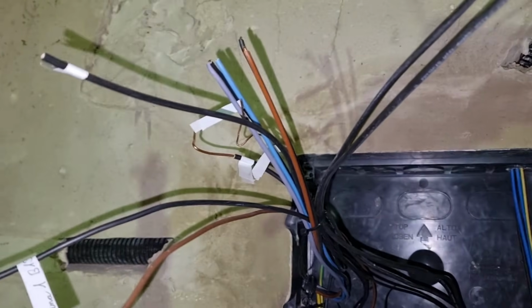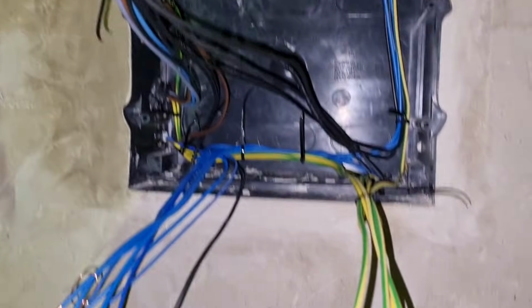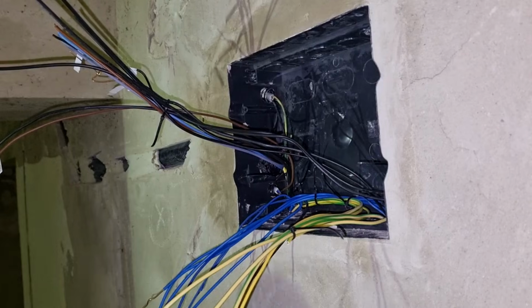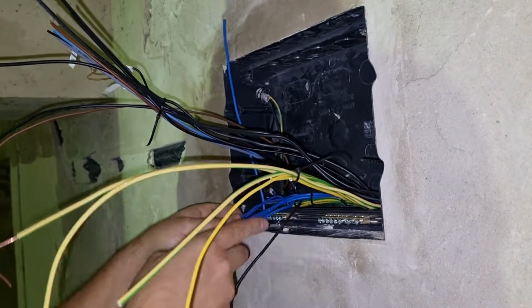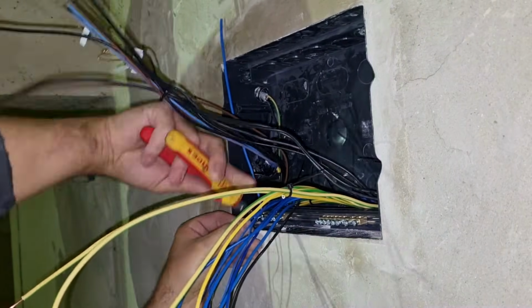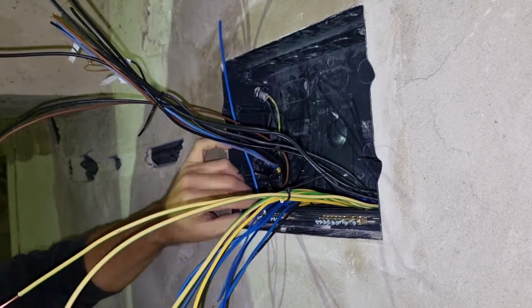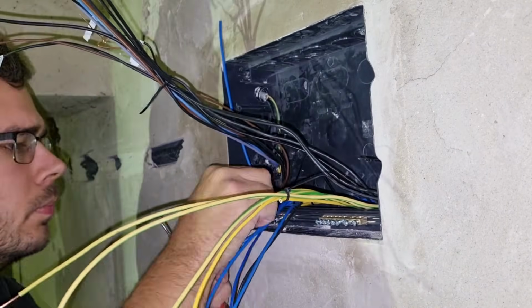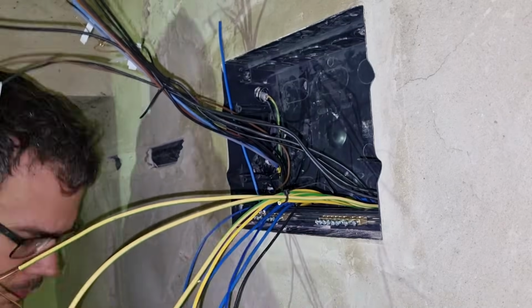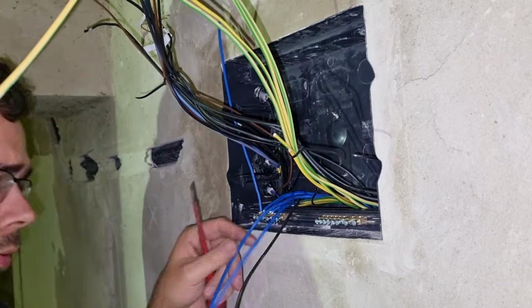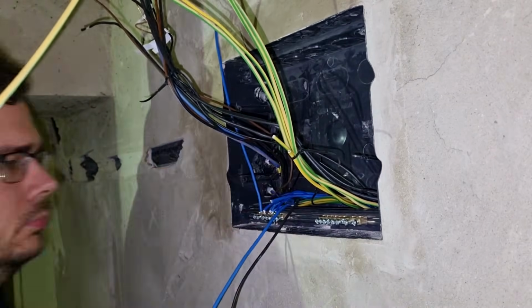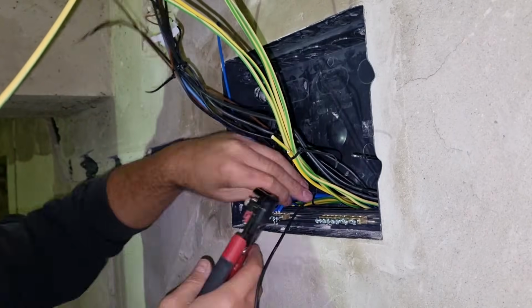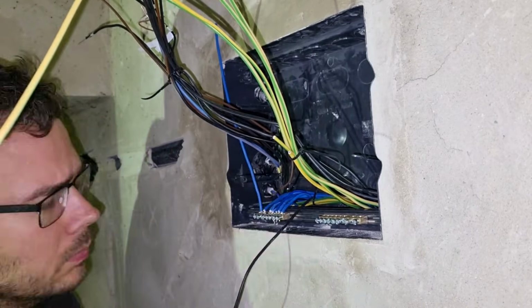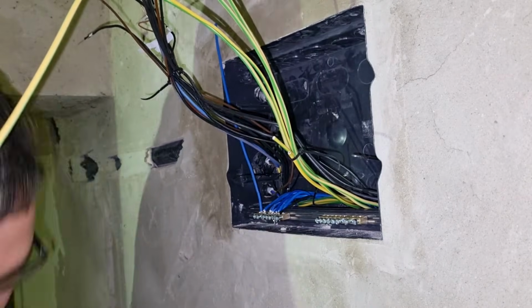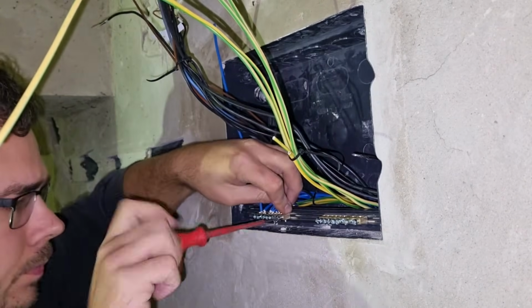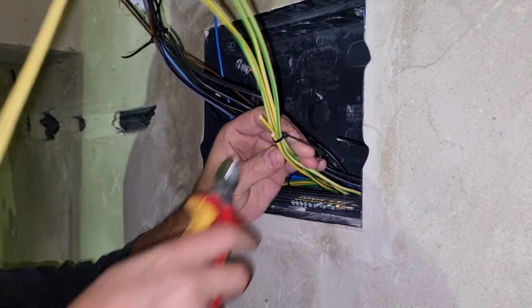When creating the distribution boards, I first separated the protective earth wires, which are green and yellow in my country, from the neutral wires, which are blue. These go to separate bus bars at the bottom of the cabinet. I tried to keep everything neat and orderly, using zip ties to guide the wires like in a military formation, which is much harder than it looks. I divided the network into 3 residual current devices.